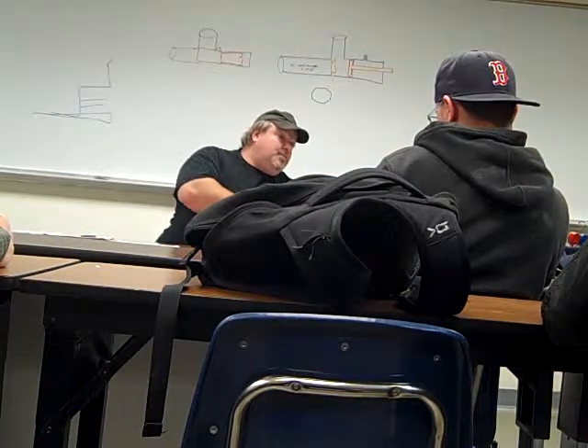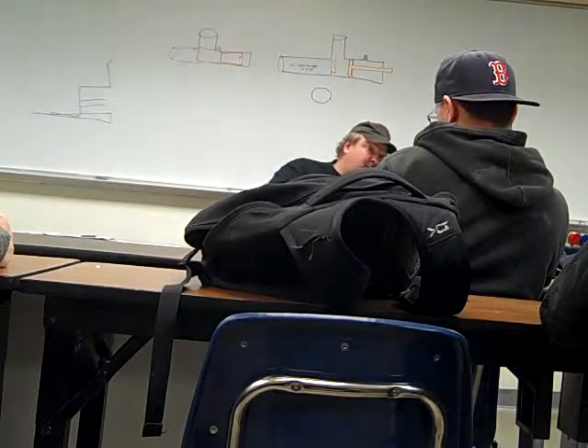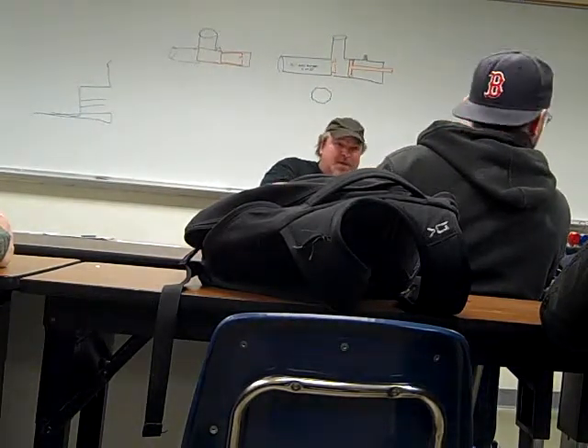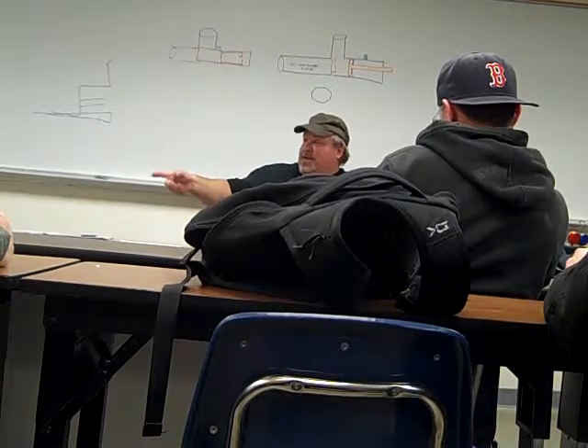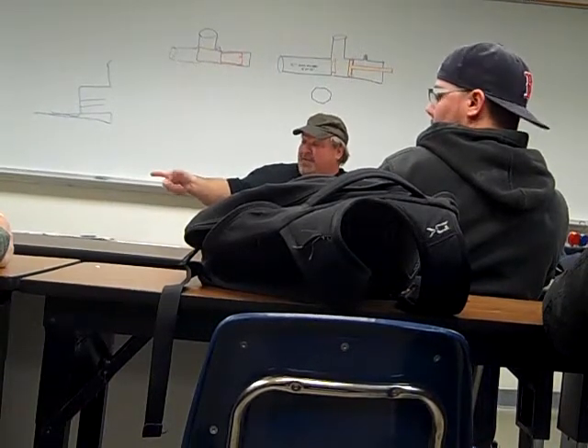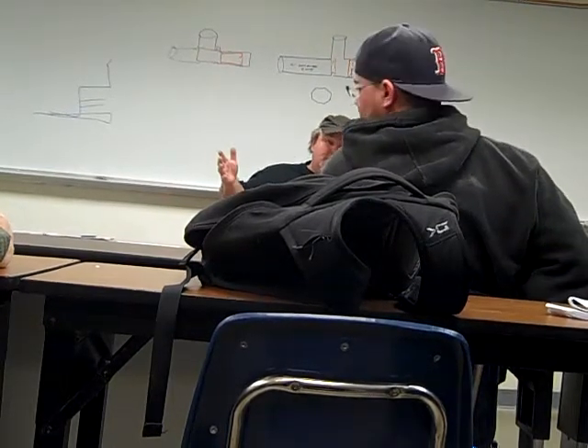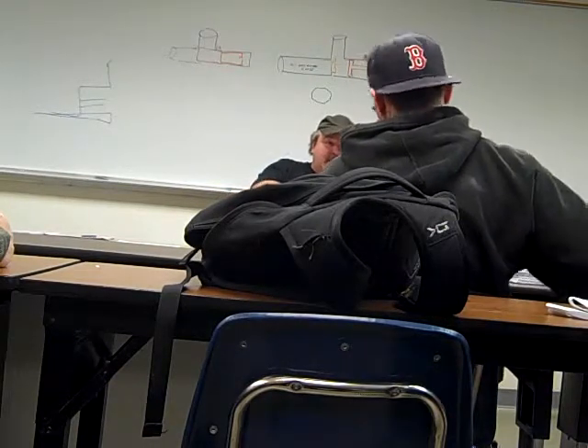You use a regular vacuum like you got there, or like that little vacuum pump? You can use them, but it'll take you forever. They have large commercial vacuum pumps for chillers. I mean, like that little one there, I think is probably a 5 CFM, pulls 5 cubic feet of air per minute. The large ones, they've got 25 and 30 CFM pumps.